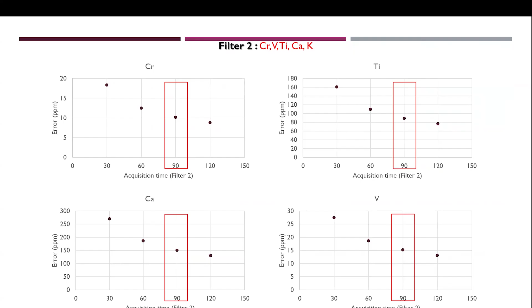Similarly, for the second filter, for the low elements, it shows results with acceptable error value for the measured elements for this filter, such as chromium, vanadium, titanium, calcium, and potassium, which were measured at 90 seconds. The third filter showed an error for barium at an acceptable rate at 60 seconds with respect to the error value noted at 90 seconds. For the fourth filter for the light elements, we can see a decrease of almost 100 ppm specifically for silica and magnesium at 120 seconds.